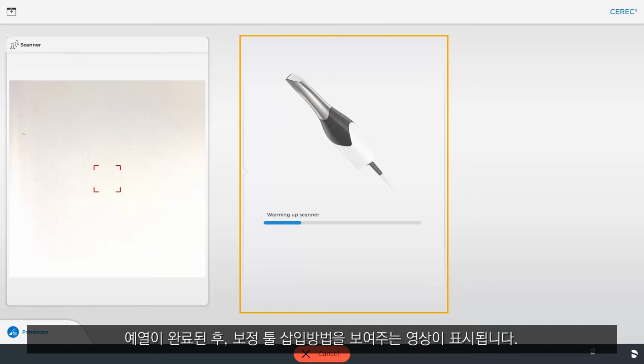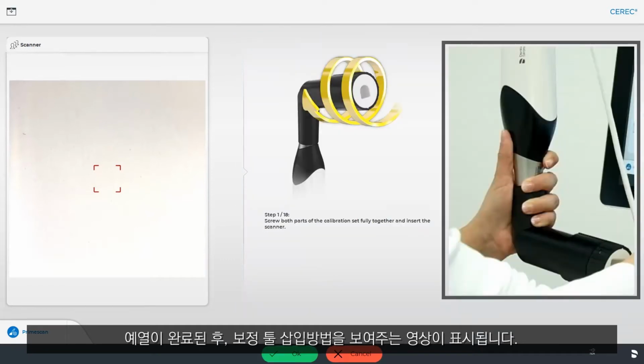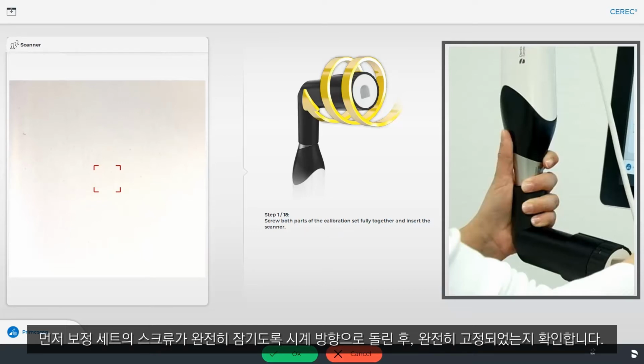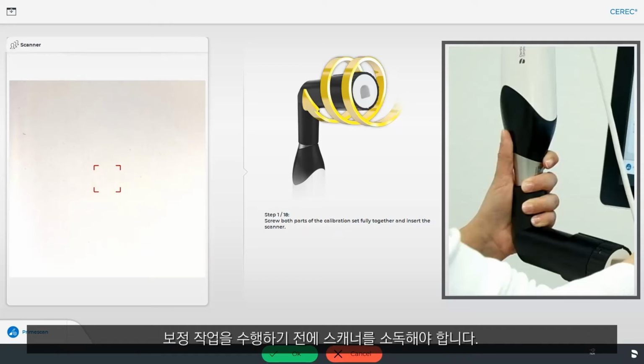After the warm-up is complete, an image showing how to attach the calibration tube appears. Alternatively, the positioning shown to the right can be applied. First, ensure that the external calibration set screw is fully screwed in with a clockwise motion until it gently locks into place. Before doing this, the scanner should be wipe disinfected.